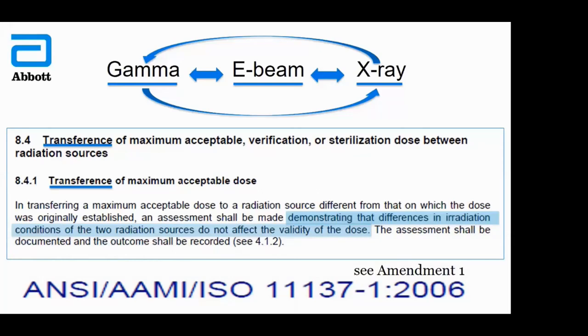So again, transference of max acceptable dose. When we talk about product qualification, we're all about that. The verification or sterilization dose has to do with lethality, which is quite simple, as we'll see in case studies. For the max acceptable dose, what's in the body of the standard is: in transferring a max acceptable dose to a radiation source different from that on which the dose was originally established, an assessment shall be made demonstrating that differences in irradiation conditions of the two radiation sources do not affect the validity of the dose.